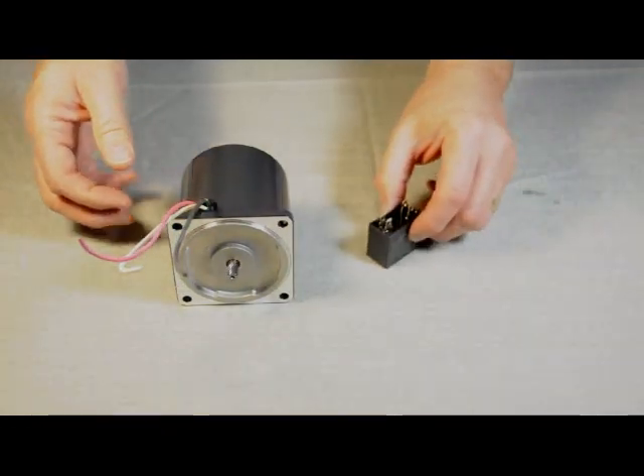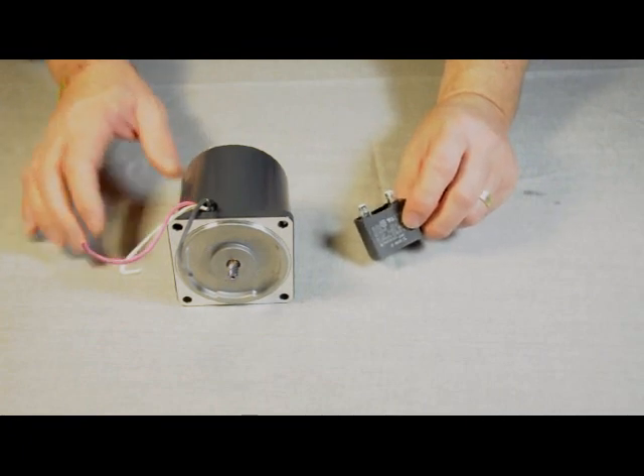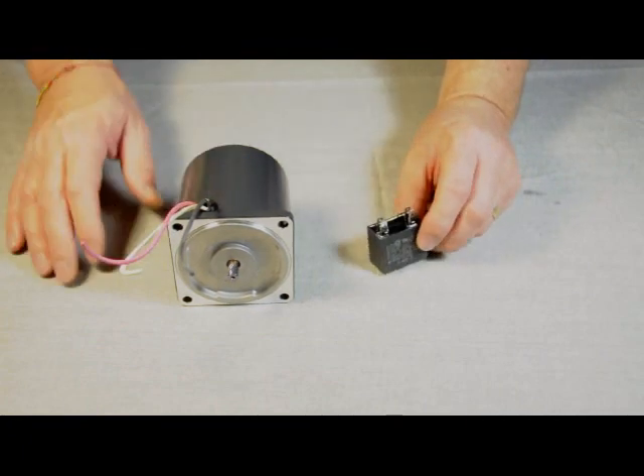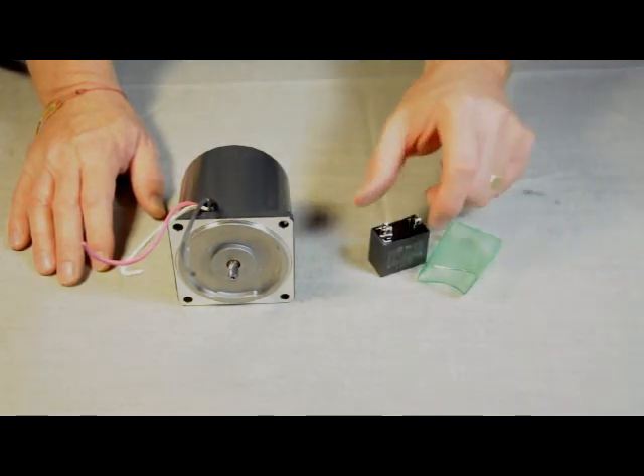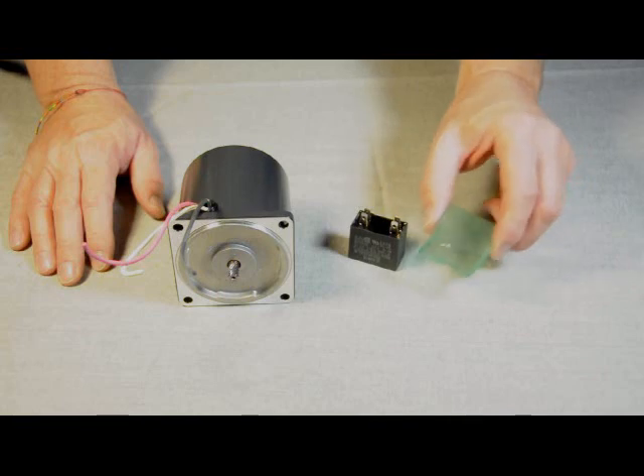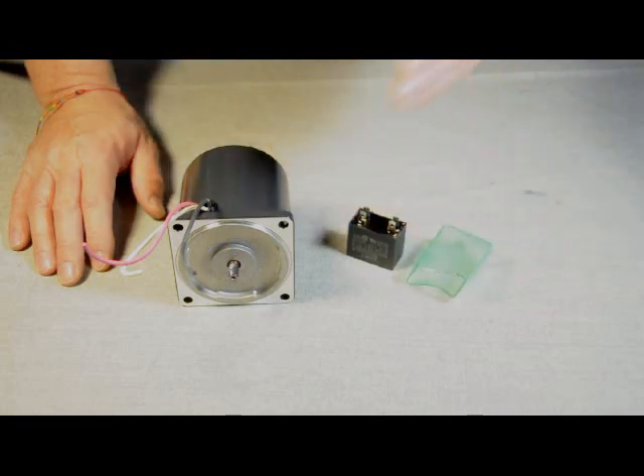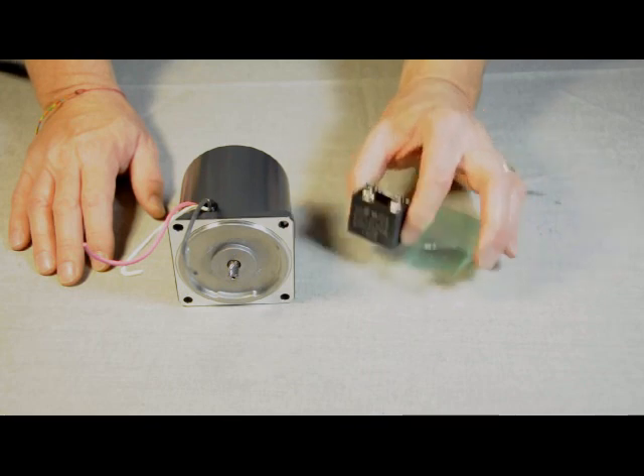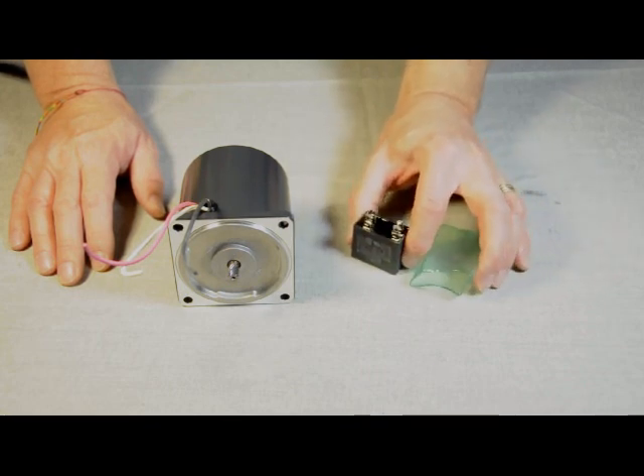The advantage of the conduit box is the capacitor, which comes with every motor where it's needed, is inside the conduit box. When we sell the terminal box or flying lead motor, you get a capacitor and a boot as well, of course only where it's needed. The 230 volt three phase does not need a capacitor for starting.